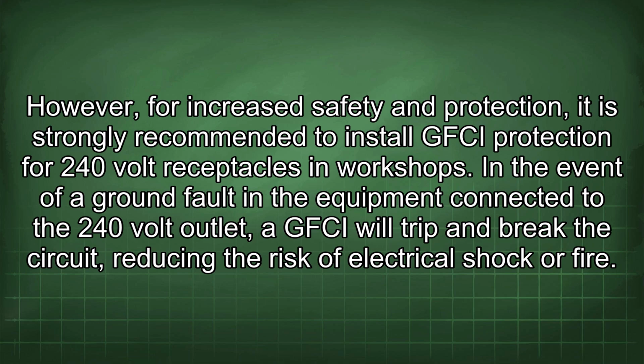However, for increased safety and protection, it is strongly recommended to install GFCI protection for 240-volt receptacles in workshops. In the event of a ground fault in the equipment connected to the 240-volt outlet, a GFCI will trip and break the circuit, reducing the risk of electrical shock or fire.